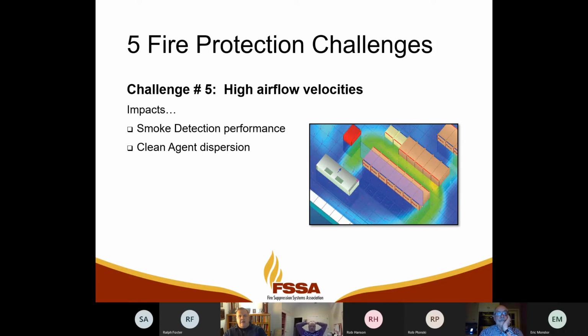And so that was like a 2-phase study. After phase 2, there was kind of enough information for the NFPA 75 and 76 technical committees to write new information into those standards to address those high airflow conditions. Most of that research landed in new requirements in those areas. It didn't really change NFPA 72 much, and we'll talk about that kind of at the end.